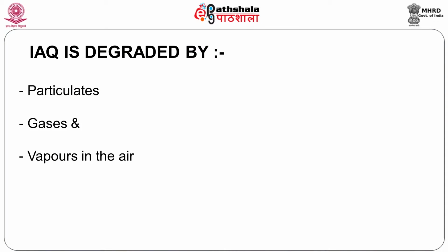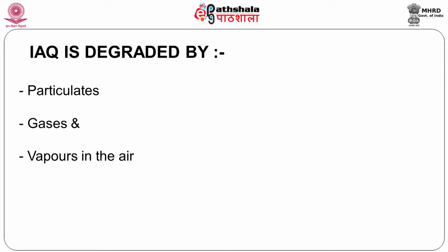Now, indoor air quality, when we were talking of it, gets degraded by elements like particulates, by elements like gases, by elements like vapors. Particulates, very simply, you just catch them in a filter, they are trapped. Things like gaseous and vapors require special filtration. They require activated charcoal filters, they require gas absorbers. Now, that will not be within the ken of this talk, but knowing about these parameters and a requirement that they can impose upon you is nice to have.